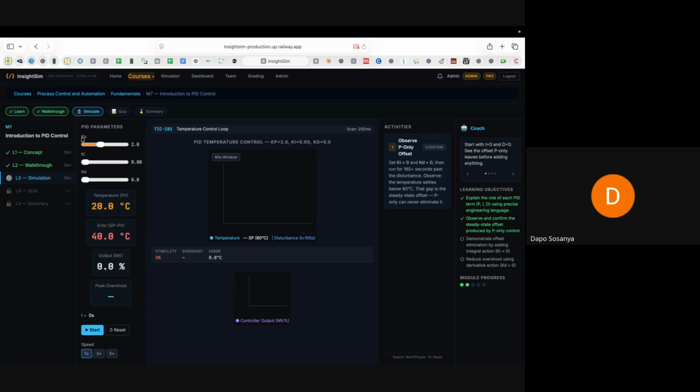So these are two different things, right? How do I explain this now? Direct acting controllers, reverse acting controllers, they are just what they are. You need to have that mindset when you're using a direct acting controller with a valve, for example, that is either fail close or fail open.